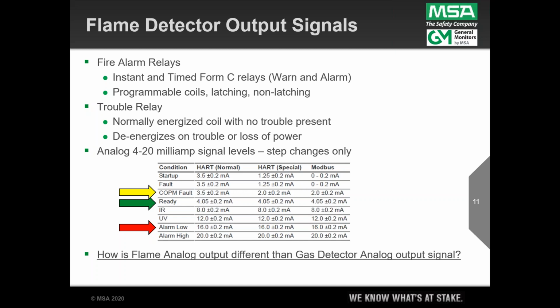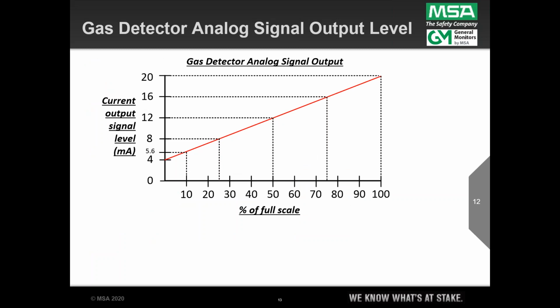And I like to put this out there for any new technicians or someone just not experienced with these flame detectors, and I ask this question to the audience: how is this different than a gas detector's analog signal? Well, that's what this slide represents, and I won't take long on this, but the vertical axis is our 4 to 20 milliamp signal, in milliamps, and so 4 we know is normal, and then on the horizontal axis is our percent of full scale. So if it's an LEL gas detector, sure enough, if the measured gas concentration in the measurement cavity is 50% of LEL, well, if you go up to the red line and go over, then we should see 12 milliamps out of our transmitter, right?